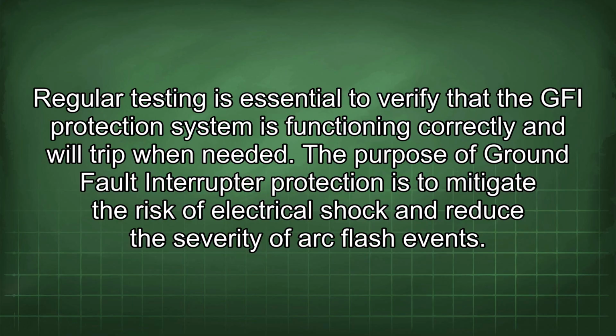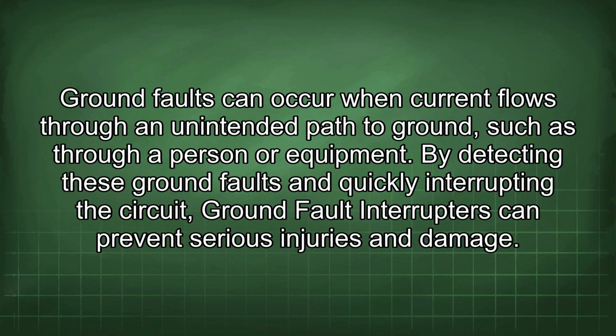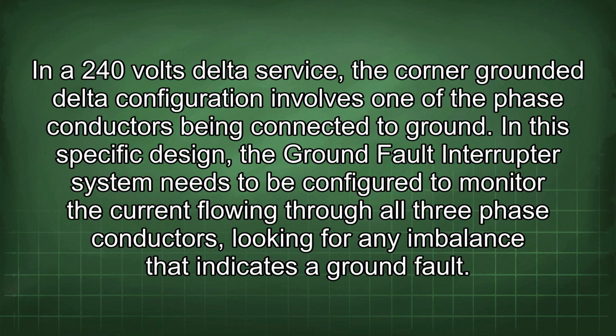The purpose of ground fault interrupter protection is to mitigate the risk of electrical shock and reduce the severity of arc flash events. Ground faults can occur when current flows through an unintended path to ground, such as through a person or equipment. By detecting these ground faults and quickly interrupting the circuit, ground fault interrupters can prevent serious injuries and damage. In a 240 volts delta service, the corner grounded delta configuration involves one of the phase conductors being connected to ground. In this specific design, the ground fault interrupter system needs to be configured to monitor the current flowing through all three phase conductors, looking for any imbalance that indicates a ground fault.